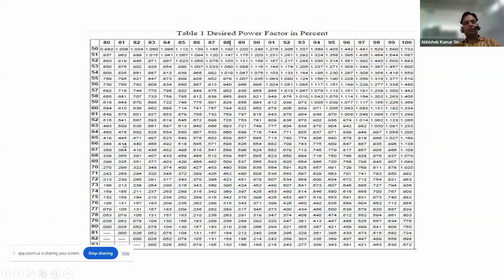Now this is a table. Suppose our initial power factor is 0.8 and we want to achieve 0.95, and our load is 100 kilowatt. You will see this table and come to this point, and you will see that it is 0.421. It means that to achieve 0.95 from 0.8, we have to multiply the 100 kilowatt load by 0.421. It means we require about 42 kVAr to improve the power factor, roughly 40 kVAr extra.